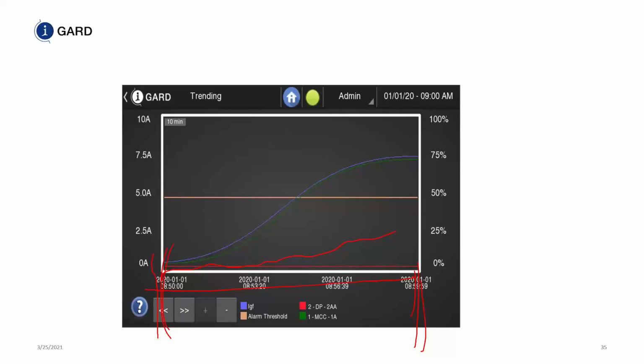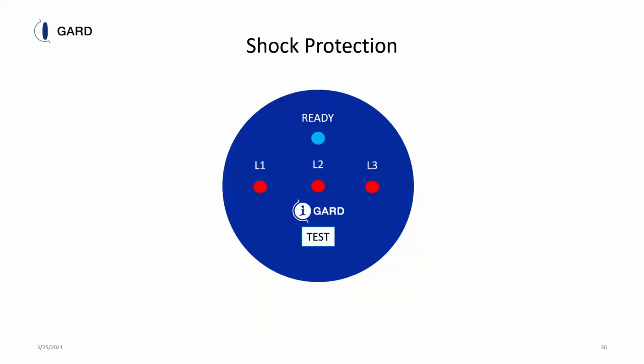But one of the things we've also discovered is a lot fewer people are being hurt by arc flash mitigation. More people are being hurt by shock than anything else. So we've developed an absence of voltage detector. If you look at the terminology in 70E and Z462, they say you have to establish an electrical safe workspace. Before you can do that, you must measure the voltage phase to phase and phase to ground, both AC and DC, and only after you've ensured that your meter works and you have a low or no voltage, determine that it is de-energized or there is an absence of voltage.